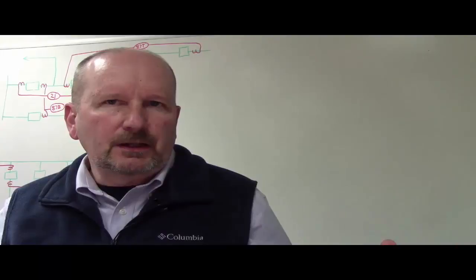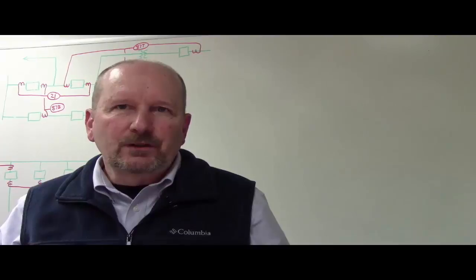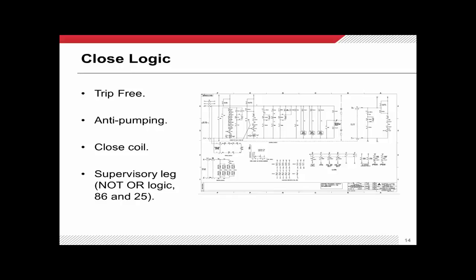We need the thing to trip and remain open, and we accomplish this through a scheme called the anti-pumping scheme, which we'll cover in just a minute. This gives all of our circuit breakers the characteristic of being trip free, and is absolutely essential for how we protect the transmission grid.